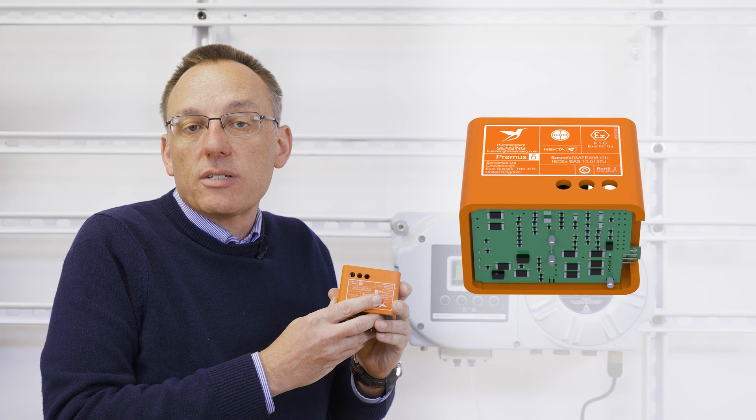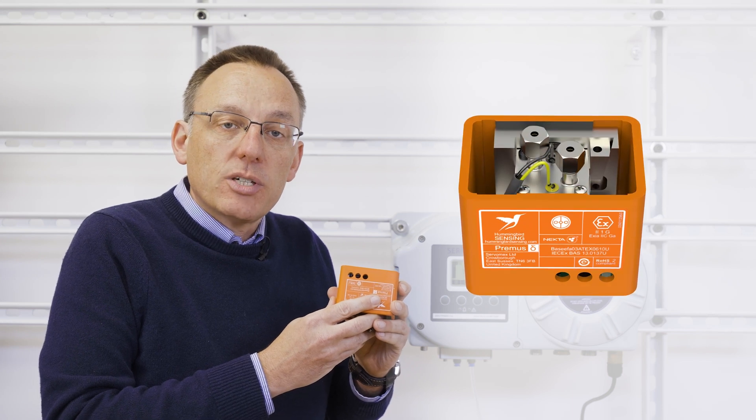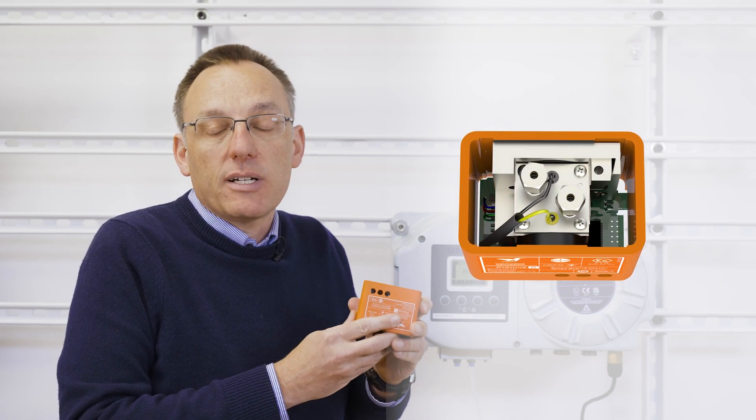This paramagnetic sensing technology is non-depleting, accurate and highly stable. It requires minimal calibration and no supply of an additional reference gas, so it ensures a long lifetime of ownership with low maintenance and running costs.